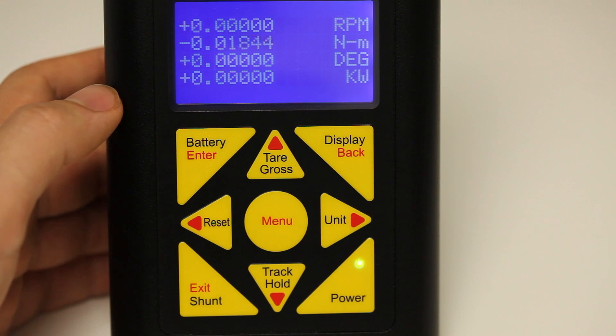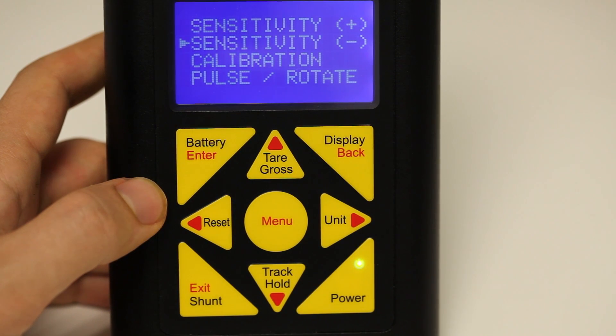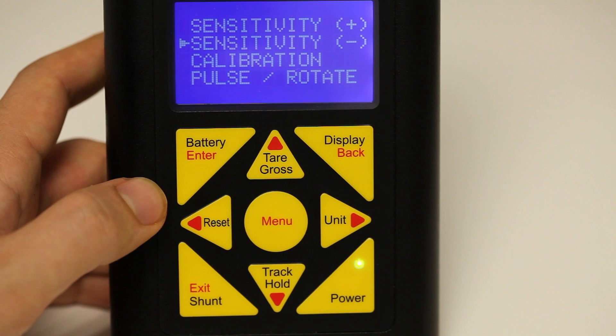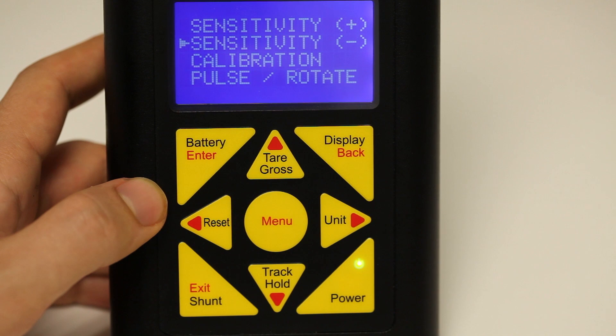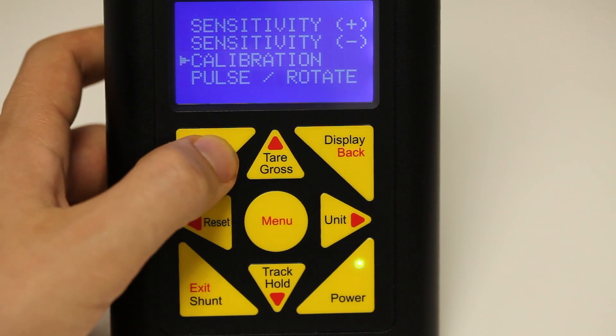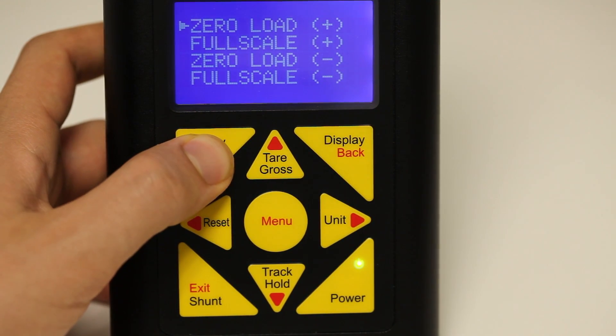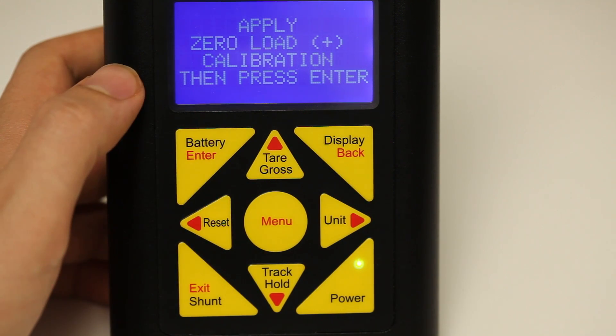This next section will show how to perform a live calibration portion of the sensor profile. To perform a live calibration, the positive sensitivity and negative sensitivity fields must be entered, if applicable. If the positive sensitivity and negative sensitivity aren't exactly known, an approximate value can be entered in. Once a live calibration is performed, the exact sensitivity positive and negative will be entered into the IHH500. After the positive and negative sensitivity have been entered, scroll down to highlight calibration. Press enter to enter into calibration. Press enter to select the zero load positive. Here, place a zero load on the load cell and press enter to capture the sensitivity from the load cell.